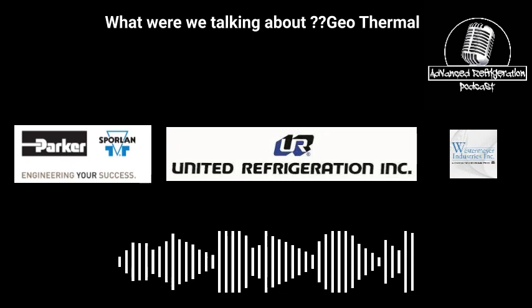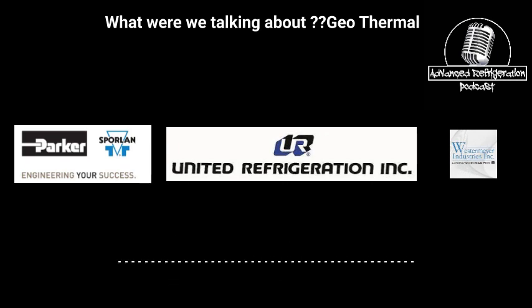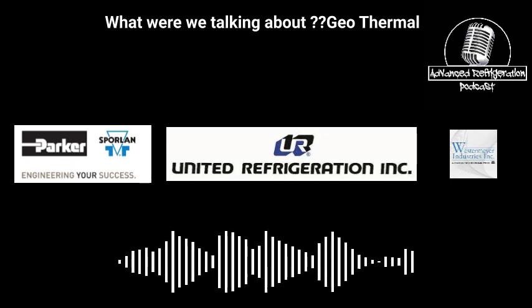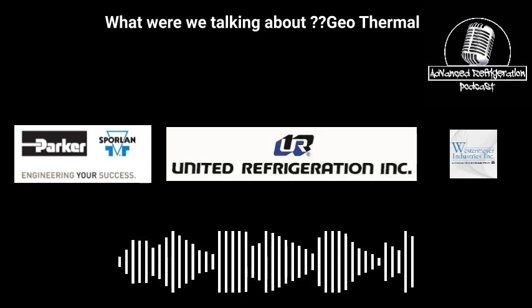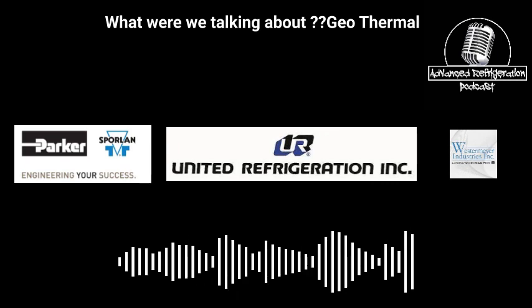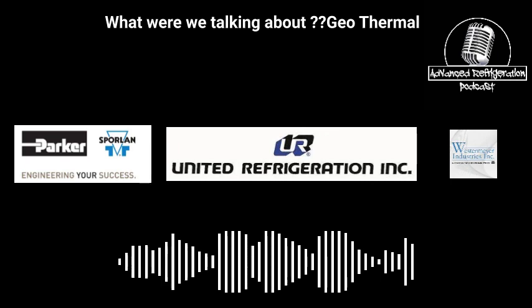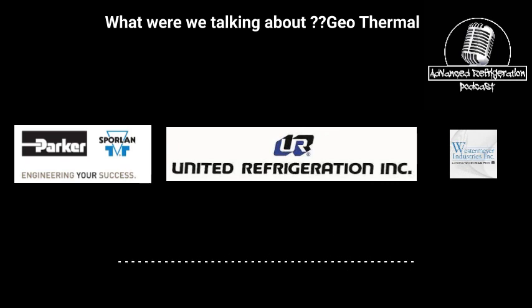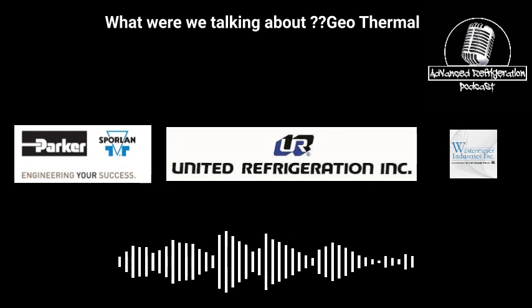Like we have one of the Walmart stores up here. It was one of the very first CO2 glycol stores. It has 38 rooftops on it that are water cooled. So wow, it's got a decent load. Mind you, the refrigeration isn't able to do all the store, but it puts in a decent amount. There's still a boiler there, and this is air heat pumps basically. They're using the towers to pull the water loop down, and then they have a boiler for supplemental heat that's heating the water loop to keep it at like 50 degrees.